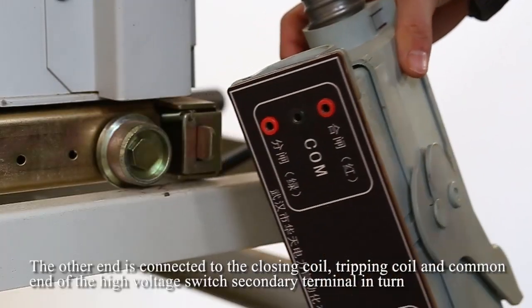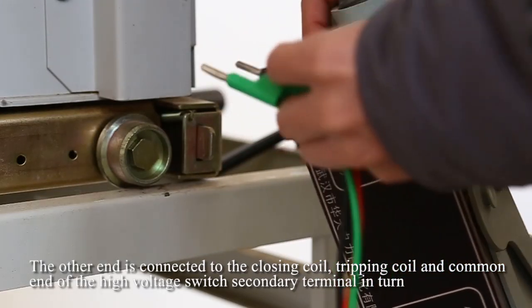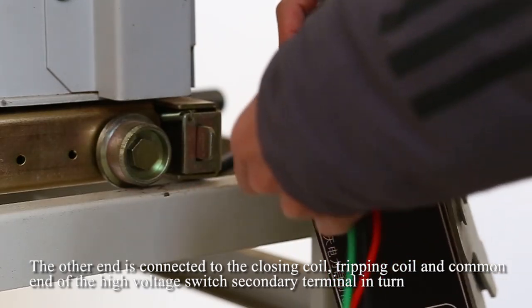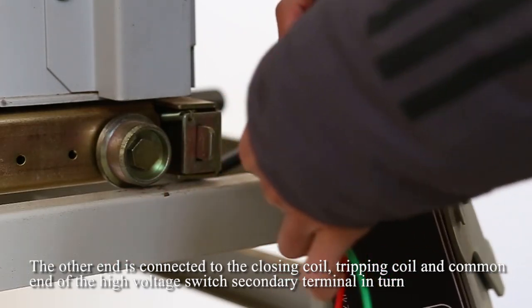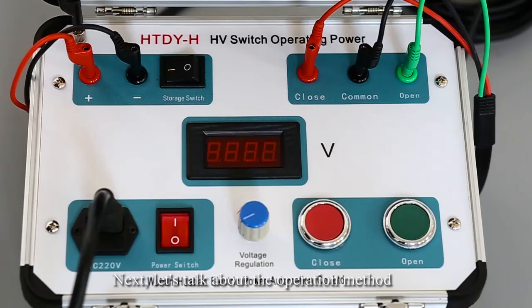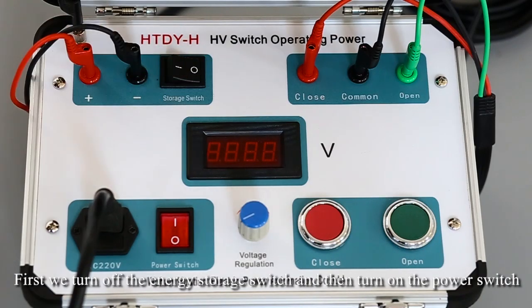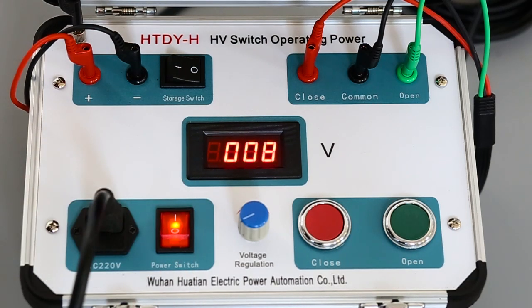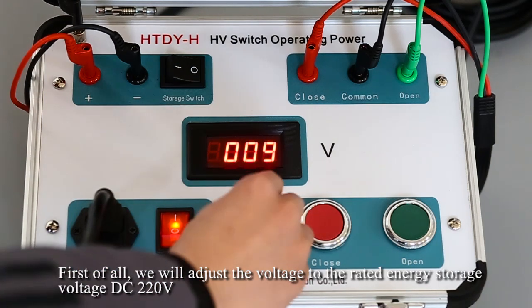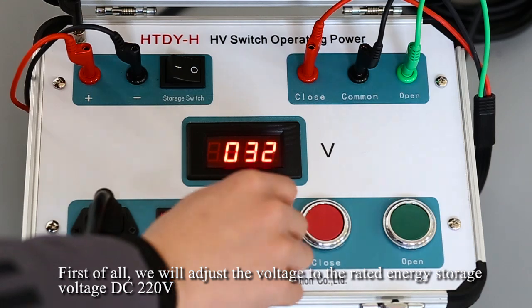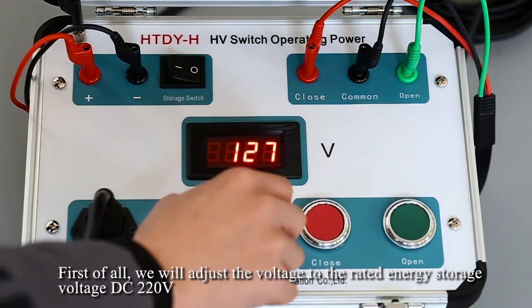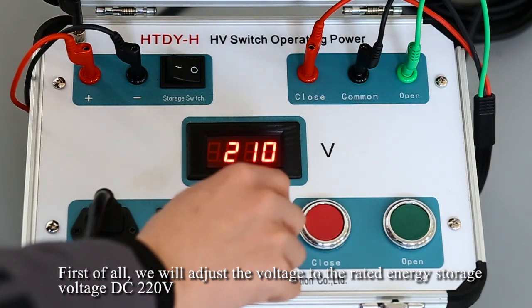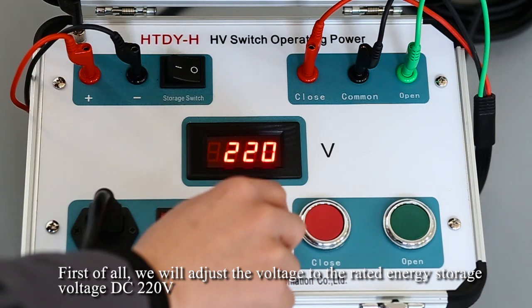The other end is connected to the closing coil, tripping coil, and common end of the high voltage switch secondary terminal in turn. Next, let's talk about the operation method. First, we turn on the energy storage switch and then turn on the power switch. The first step is to test the energy storage operation of the switch. First of all, we adjust the voltage to the rated energy storage voltage, DC 220 volts.